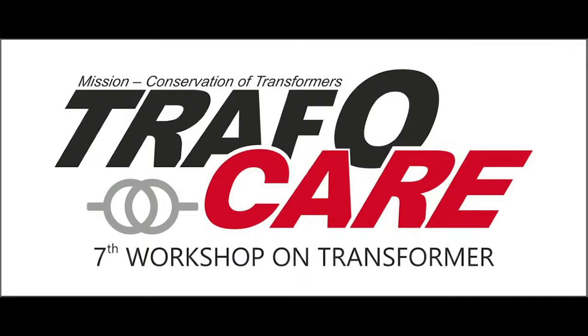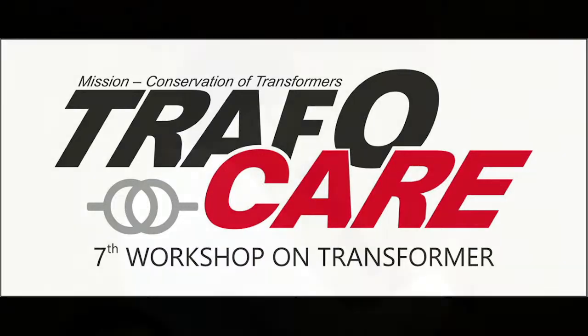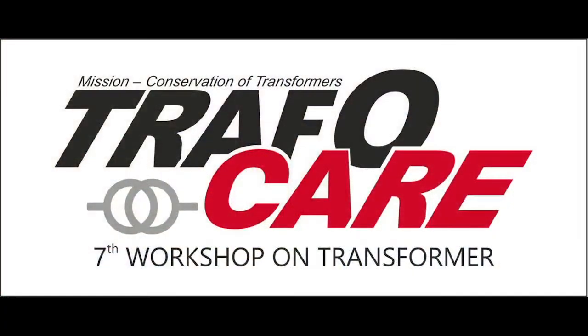Fire point, yes, fire point. One more thing, actually, you said it is allowed. Any precaution is required. There is nothing called allowed. In retrofilling, we cannot remove the entire mineral oil, so the question is about maintaining the fire point above 300. As much mineral oil gets mixed with the natural ester, its fire point will come down. It is proportionate, and that percentage we have arrived at. So there is nothing called allowing and all that.